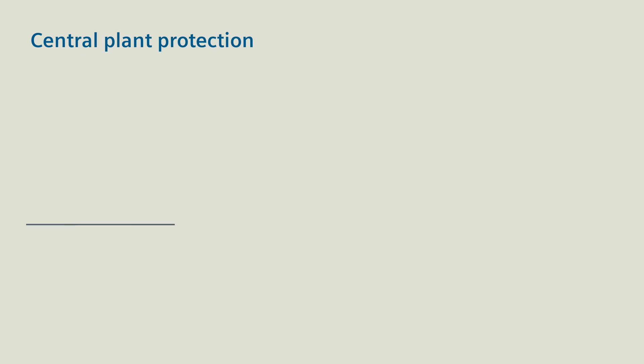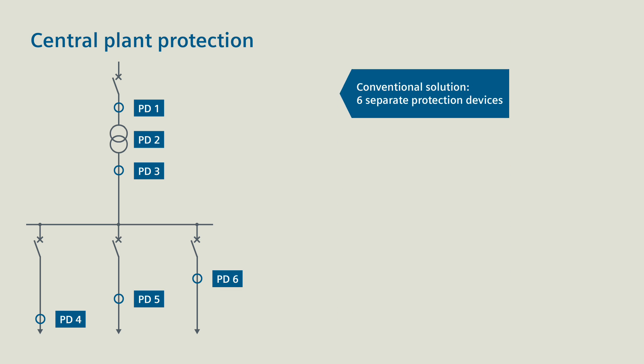Smart transition for central plant protection. With the SIPROTEC 5 process bus, it's quite easy. The initial situation is a small substation with transformer in-feed and several feeders. Solved conventionally, you would need up to six separate protection devices for this configuration.